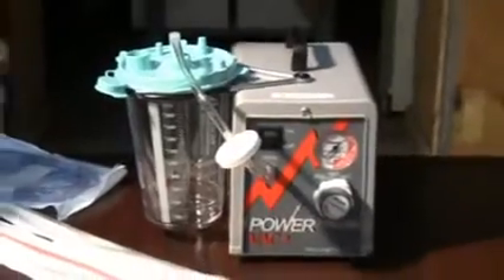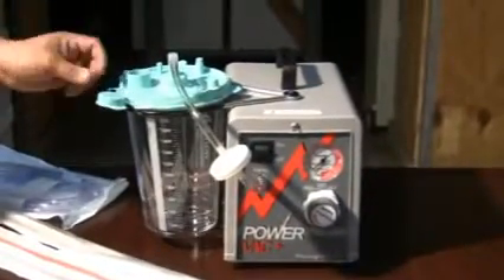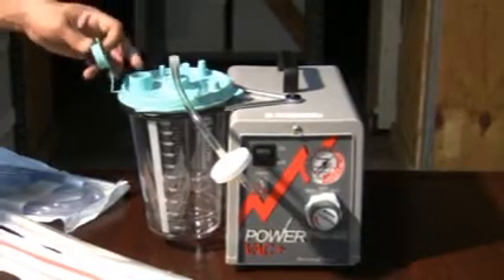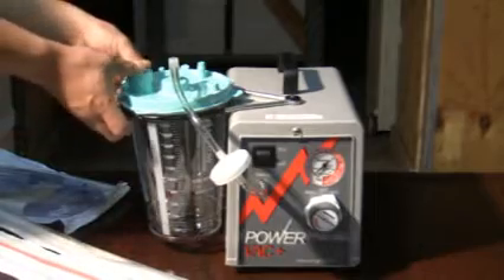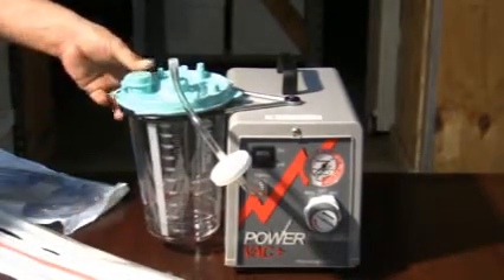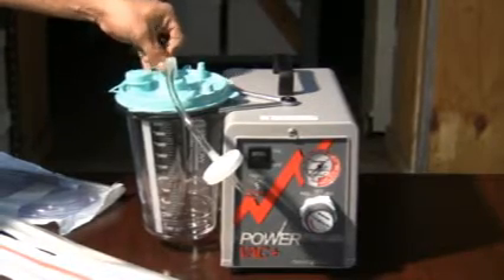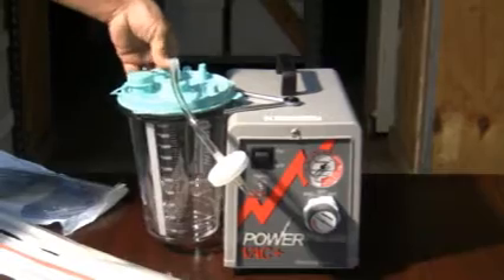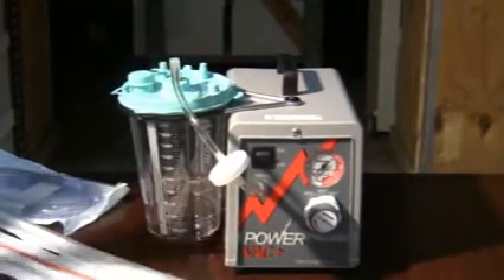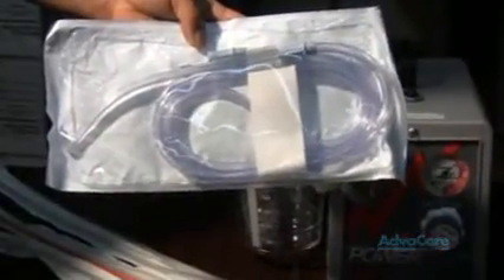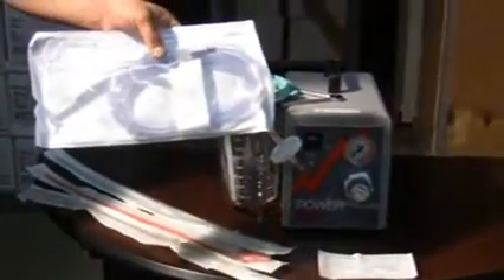To proceed with proper setup, we will cap off any openings that are left open that will not be connected to any tubings. So the large port here will be capped, and then your spare port to the side will also be capped, which leaves you with one open port here. The larger of the open ports is the port that should be connected to your Yankauer tubing and your Yankauer, if a Yankauer will be used for your suction procedure. We said the tubing is universal, so it will be used on either accessory that we had previously stated.